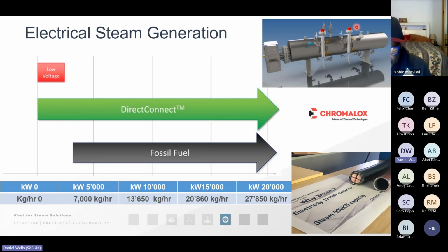I must stress that this really depends upon the client's boiler being in a good condition. And of course, if we've optimized the steam distribution system already to reduce the mass of steam that the boiler needs to produce, this becomes all the more viable. The issue that we have is exactly the same as with the electric steam boiler itself. Those elements need to be sized to ensure that the boiler is capable of producing that maximum instantaneous demand for steam at 9 o'clock on a Monday morning.